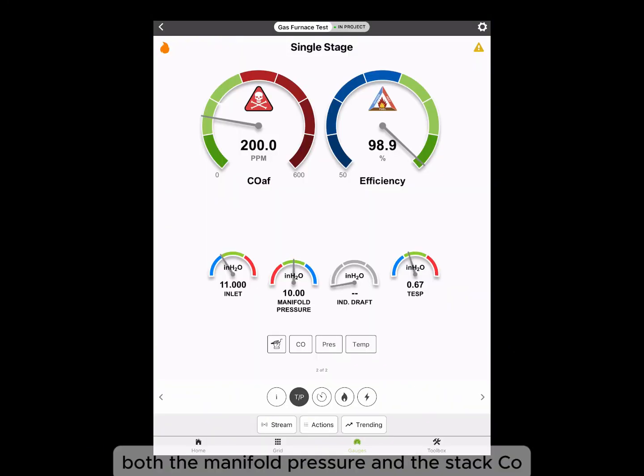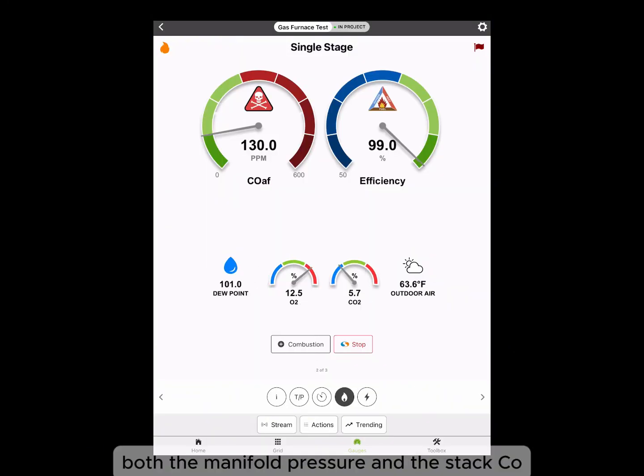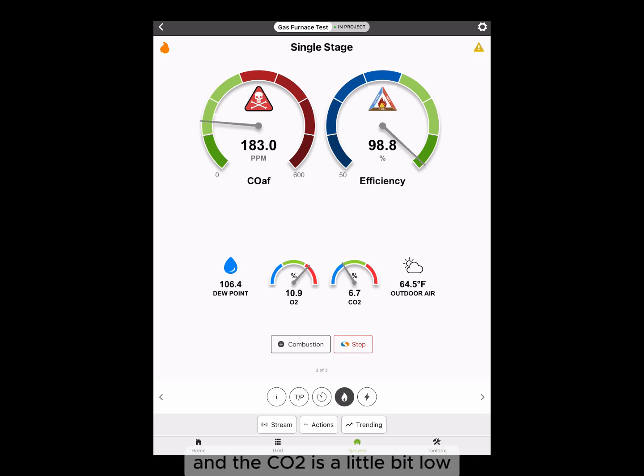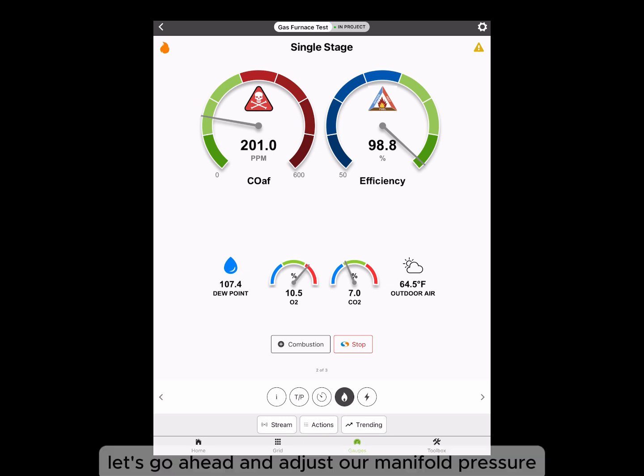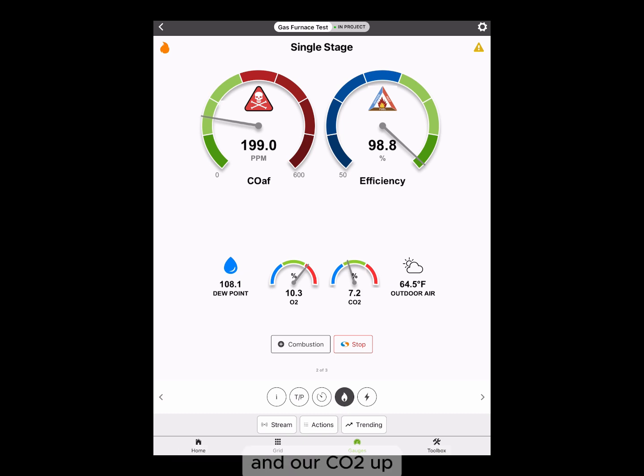As we can see here, both the manifold pressure and the stack CO seem to be pretty normal. But the oxygen is a little bit high and the CO2 is a little bit low. Let's go ahead and adjust our manifold pressure to see if we can get those readings a little bit better. A slight increase in manifold pressure is going to bring our O2 down and our CO2 up.